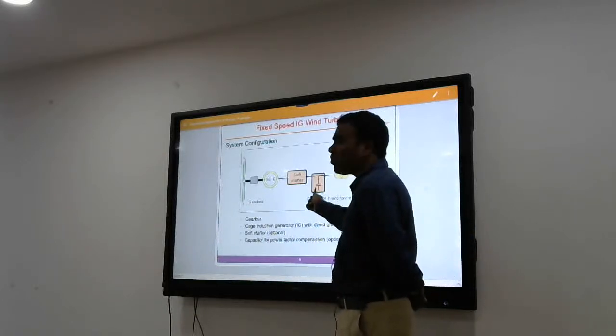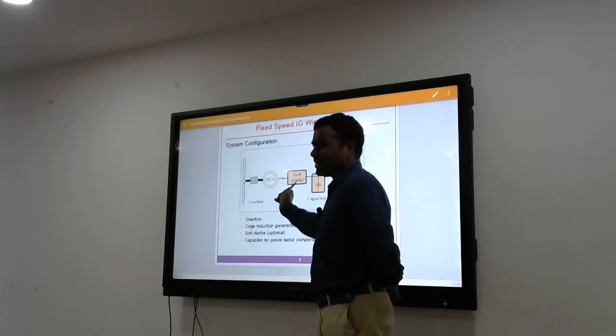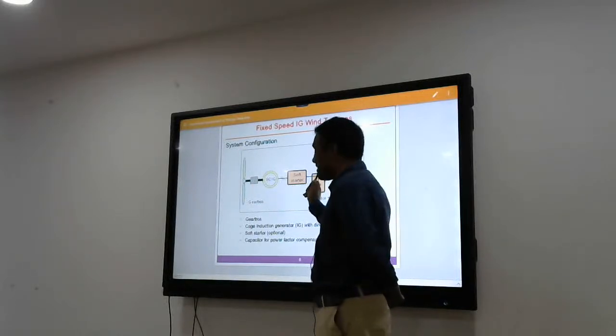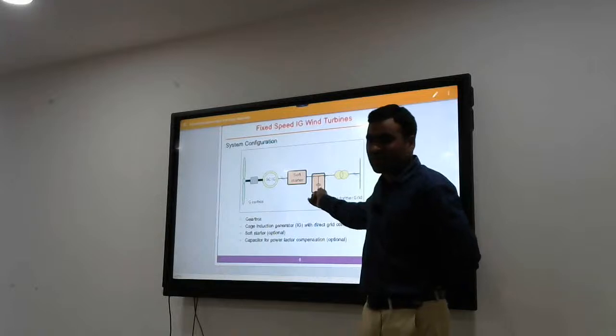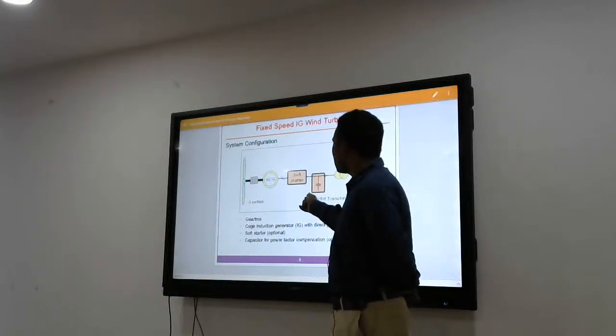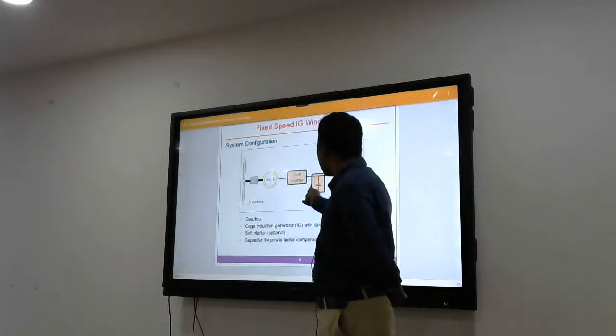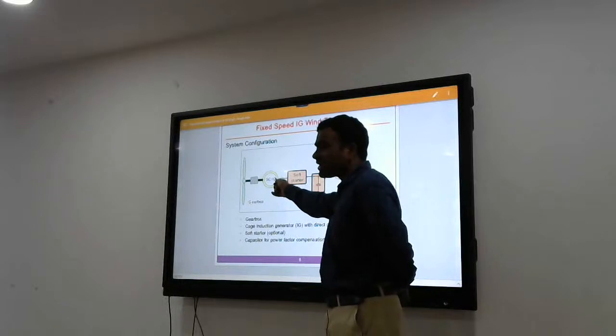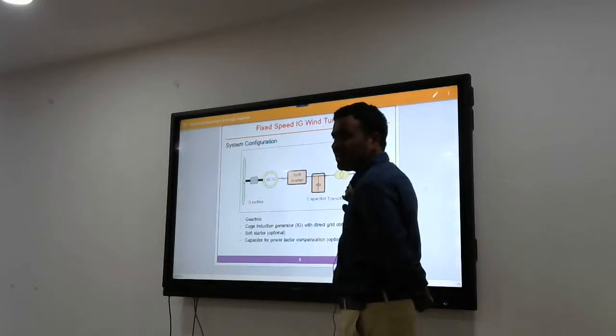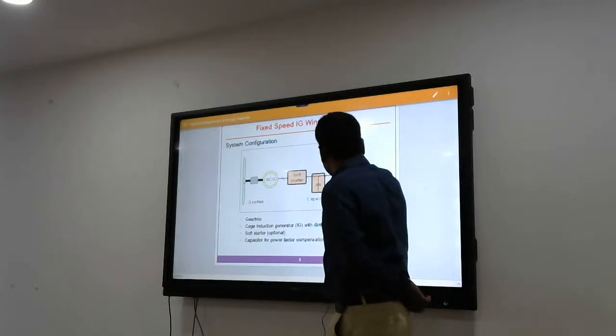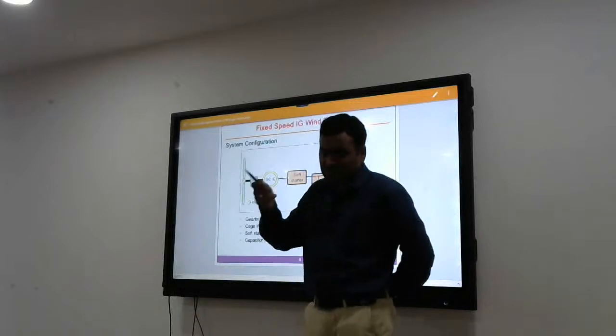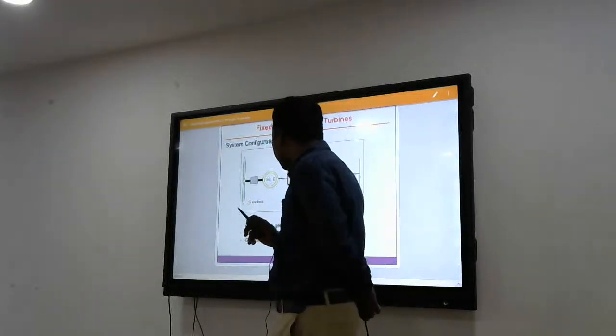So you have to connect a capacitor here to supply the required reactive power. Connecting the capacitor is a mandatory part to supply the reactive power. Even without this capacitor, this can generate power and give it to the grid, but the reactive power will be taken from the grid. But that is not recommended.